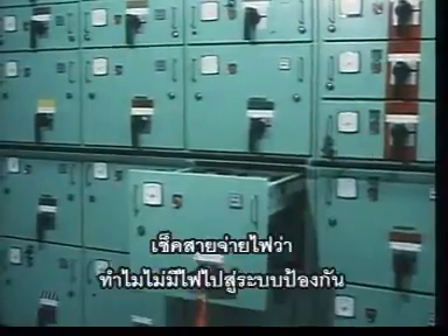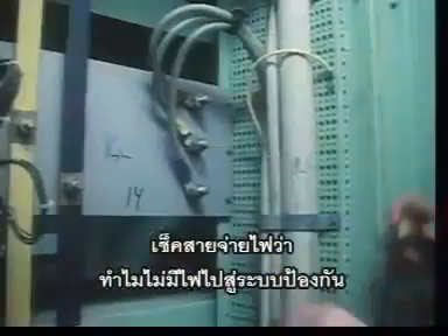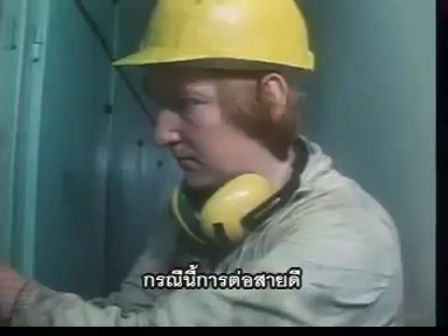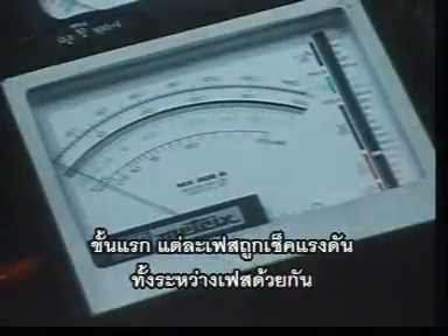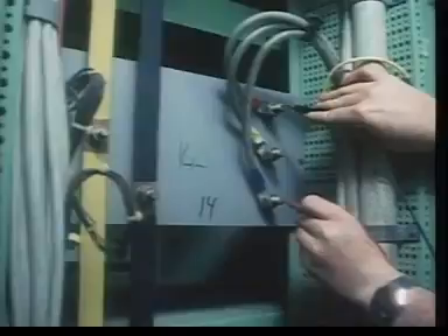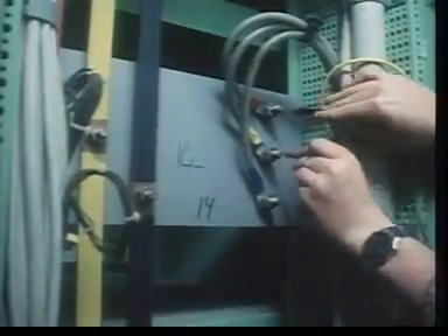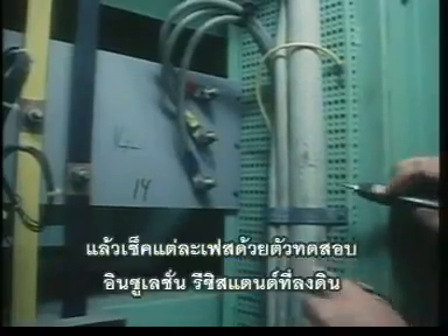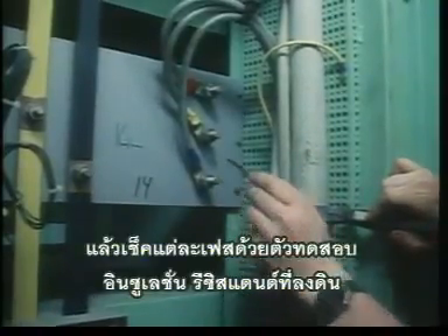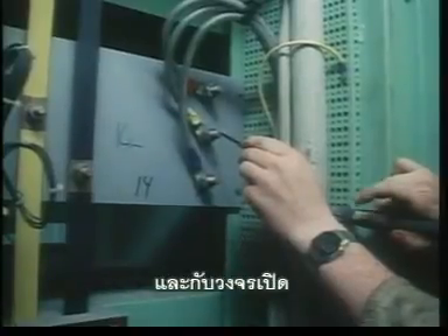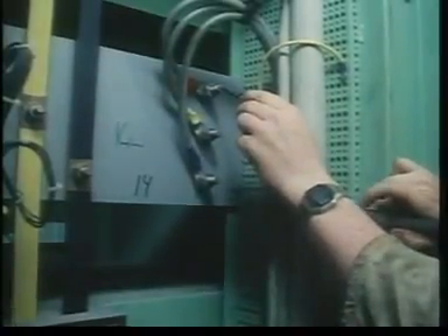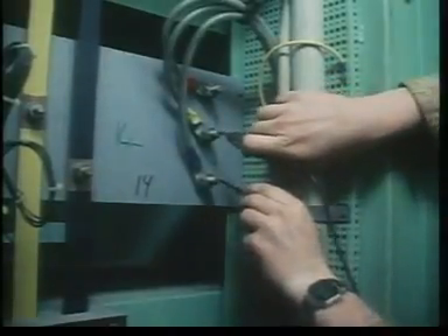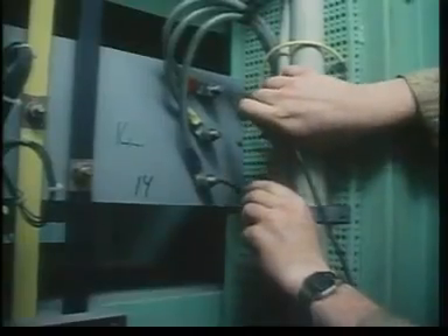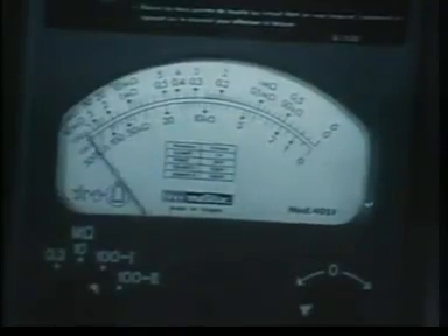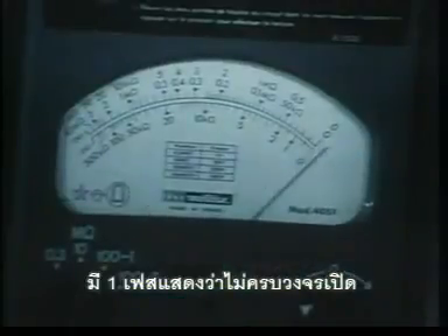At the back of the board, the feeder cables are now checked to find out why the service was isolated by the protection system. The connections here are good. First, each phase is checked for the presence of voltage, both between phases and between phases and earth. Then each phase is checked by an insulation resistance tester to earth, and then for open circuit. Although one phase has shown open circuit, you check all three phases.